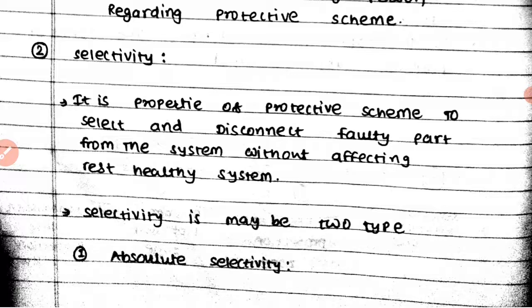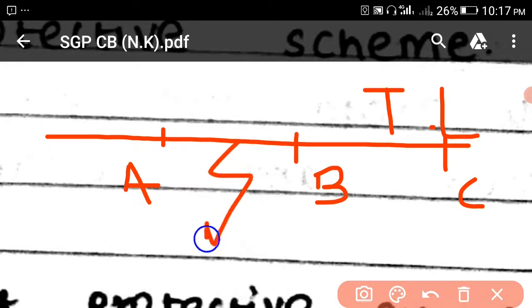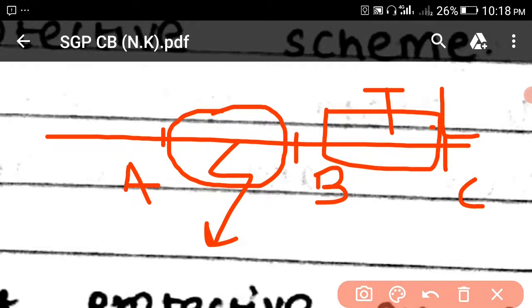The second requirement is selectivity. Selectivity is the property of a protective scheme to select and disconnect only the faulty part from the system without affecting the rest of the system. For example, on a transmission line with points A, B, and C — if a fault occurs between A and B, only the AB part is disconnected. Once the fault is cleared, the AB part reconnects, while the BC part is never removed. This is called selectivity.